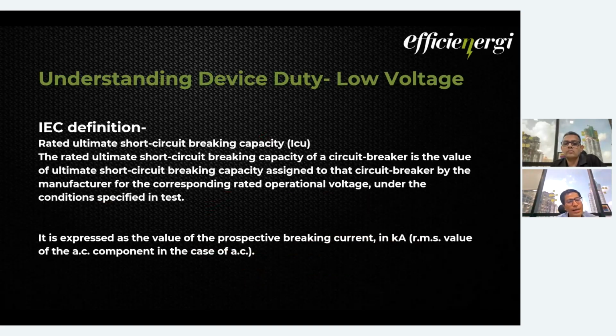Then it's the rated ultimate short circuit breaking capacity. Now we have seen what short circuit breaking capacity is. Short circuit breaking capacity has ICU and ICS. ICU means the rated ultimate short circuit breaking capacity of a circuit breaker is the value assigned to the circuit breaker by the manufacturer. Again, every definition will have the same answer: it is an assigned value, basically assigned by the manufacturer based on certain manufacturing processes.